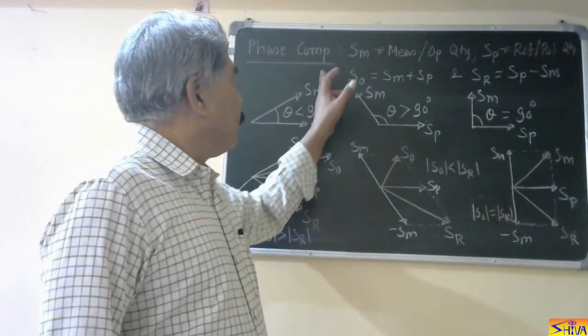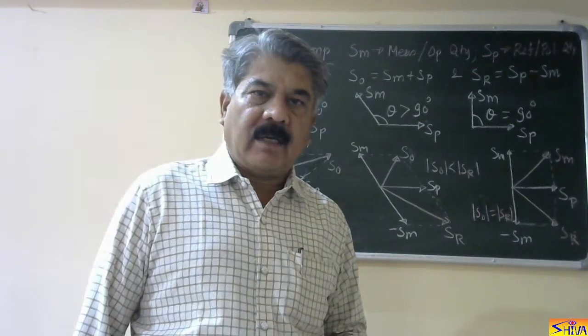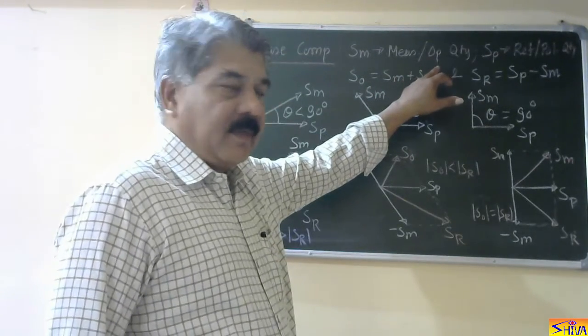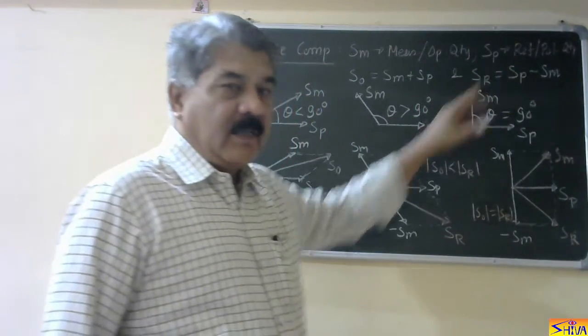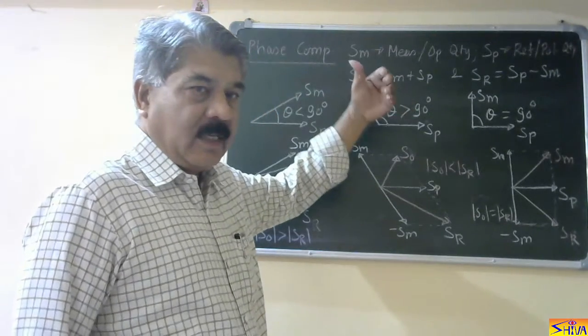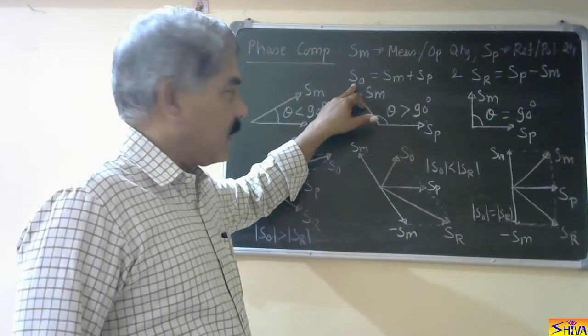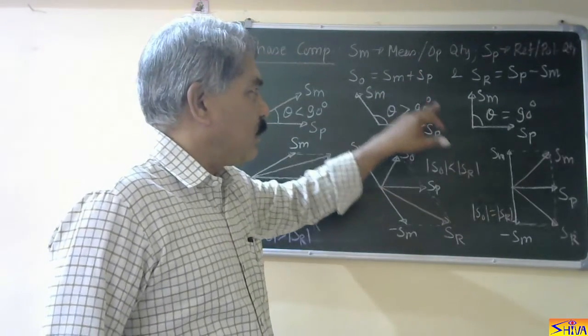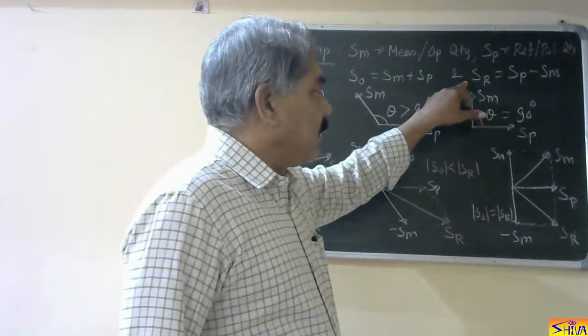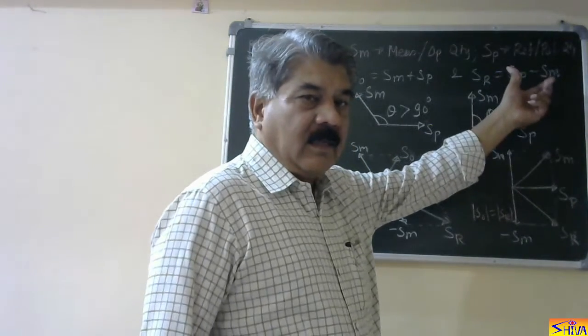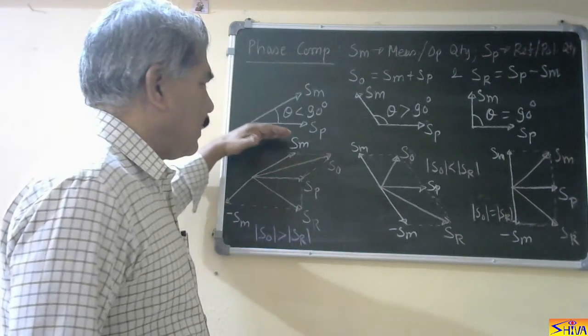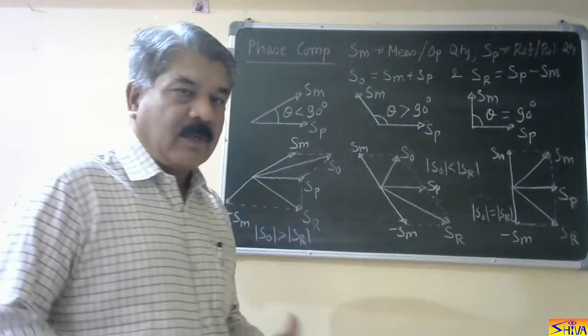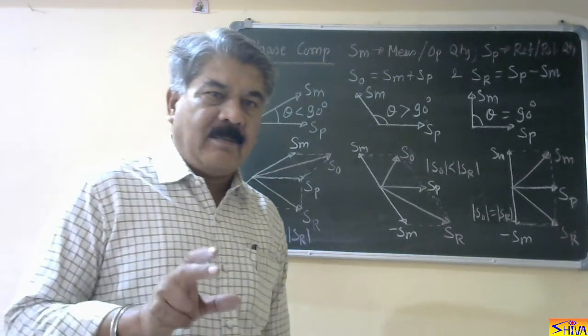Now I will consider the inherent phase comparator. SM is the measured or operating quantity for the phase comparator. SP is the polarizing or reference quantity. These quantities are changed to their sum and difference: SO, the operating quantity for the amplitude comparator, is obtained by SM plus SP, and SR, the reference quantity for the amplitude comparator, is obtained by SP minus SM. For simplicity, the amplitude of both quantities is considered the same in all three conditions.